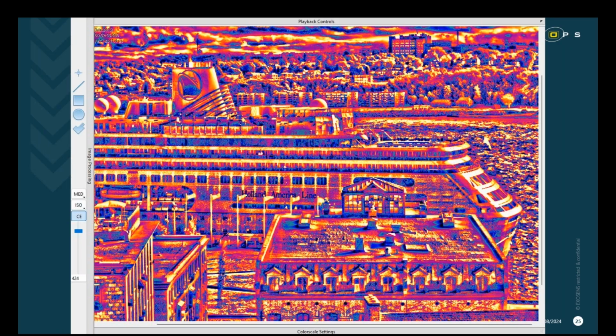Quite a bit of definition increase across these colors. So obviously, it does spread the color scale to a point where multiple colors may indicate multiple temperatures in the scene, so you do have to be wary of that. But between the original image and this contrast enhanced image, you're able to pull out quite a significant amount of detail just in the base features of Reveal IR.